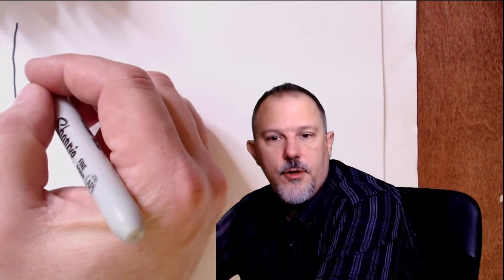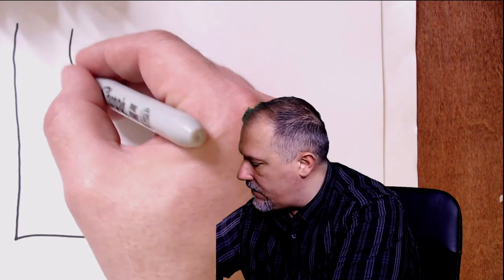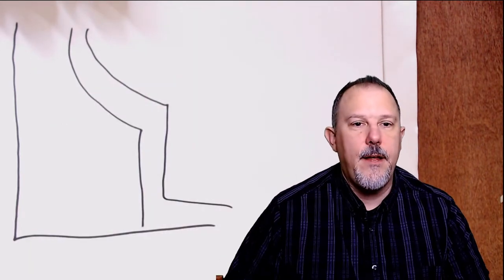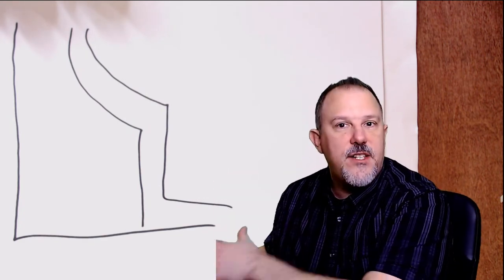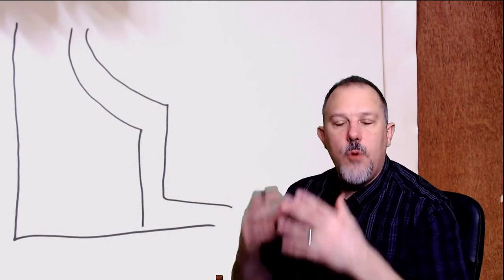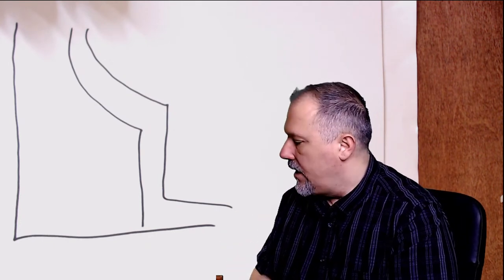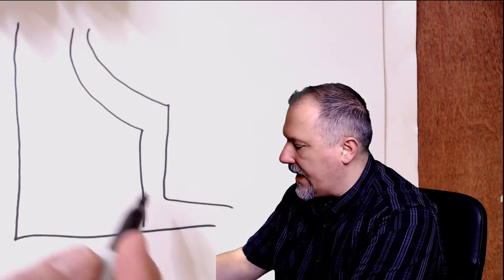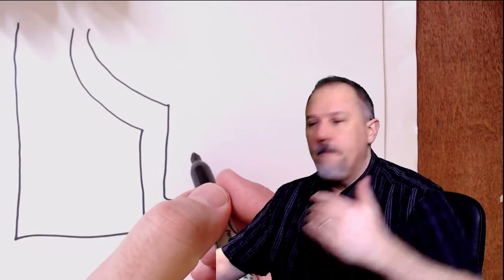All right. So your standard molded case circuit breaker had a trip curve that looked like this, right? And we're going to talk about how a circuit breaker creates this curve, where it gets it from. But this is your standard molded case circuit breaker, and you'll notice a lot of these older breakers have very fat bands. These are smaller devices. They've got an instantaneous when you start getting up closer to the service.